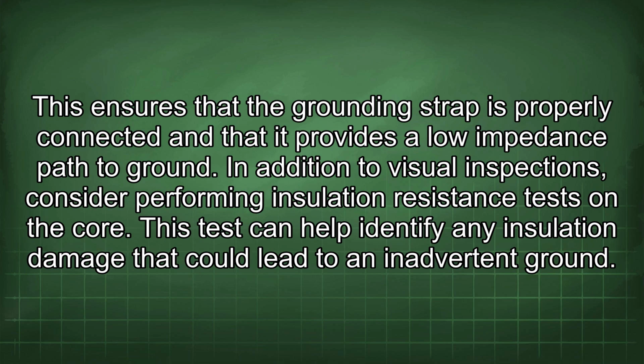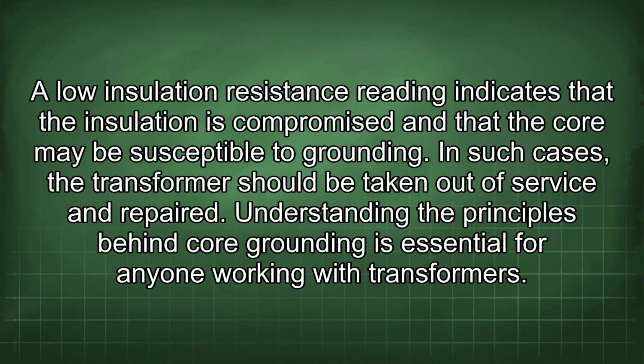In addition to visual inspections, consider performing insulation resistance tests on the core. This test can help identify any insulation damage that could lead to an inadvertent ground. A low insulation resistance reading indicates that the insulation is compromised and that the core may be susceptible to grounding. In such cases, the transformer should be taken out of service and repaired.